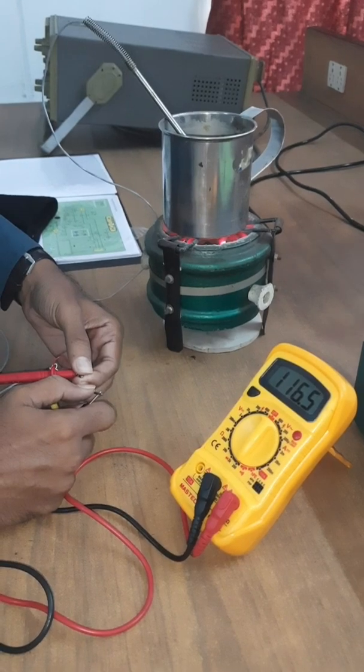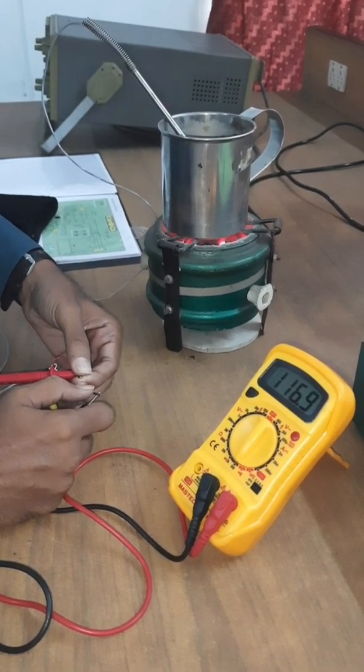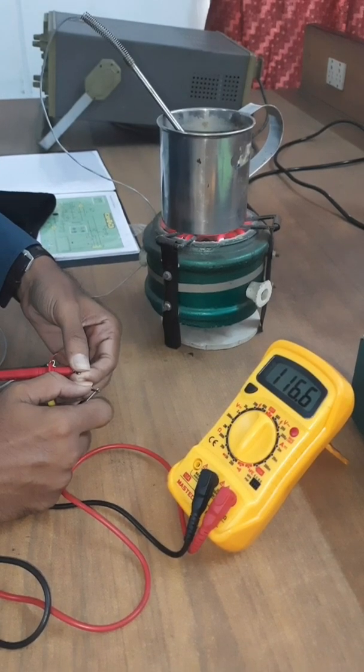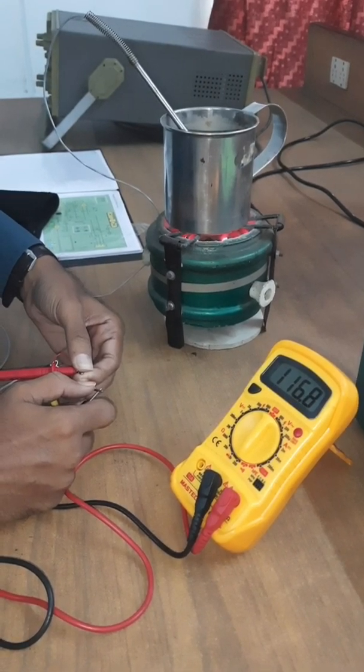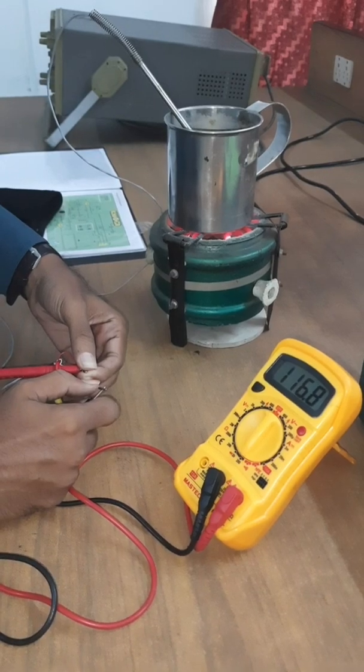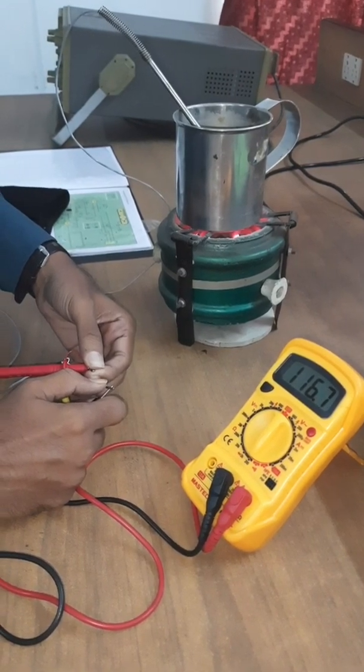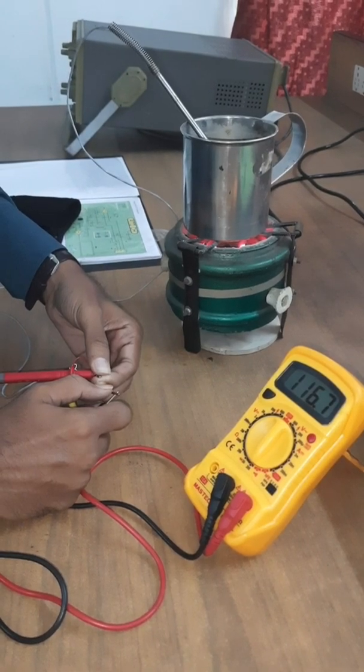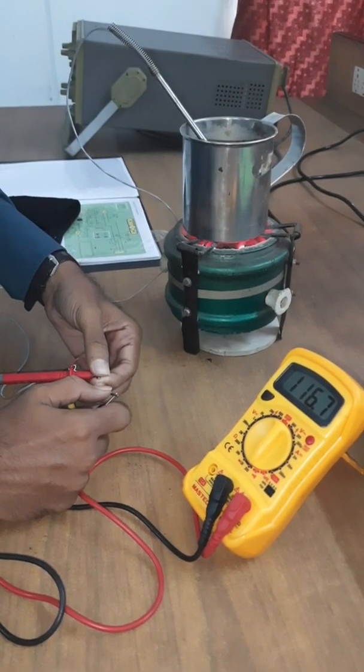It's around 116.2. What you should observe is that this resistance will keep on increasing because we are heating this process fluid and RTD being a positive temperature coefficient resistance material, its resistance will increase as temperature increases.